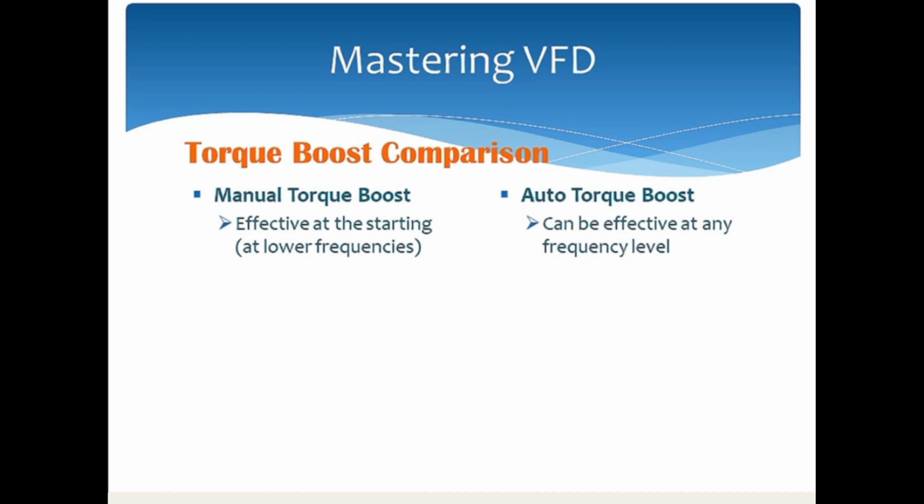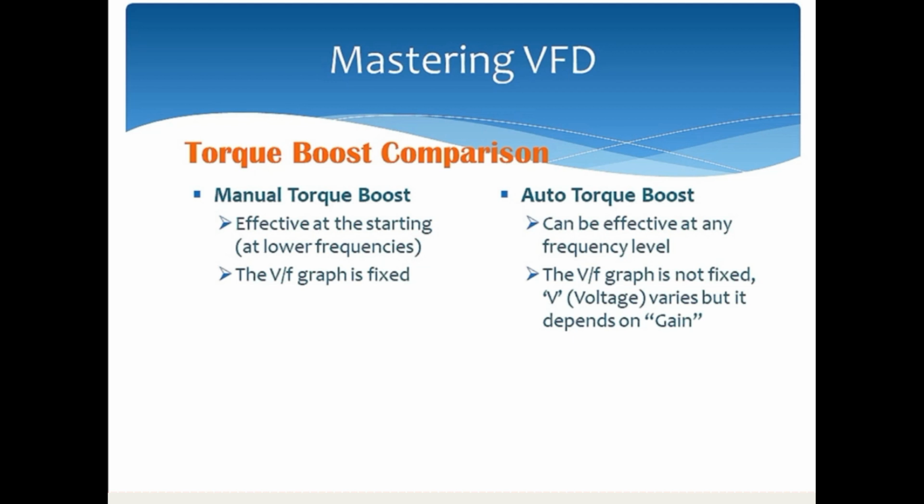Next point is, in manual torque boost, the V over F graph will remain fixed. But in auto torque boost, voltage will adjust depending on the load condition, or we can say depending on the gain, as we have seen in the graphs before. Lastly, V over F is good in terms of precision. Let's say we are using an elevator application.